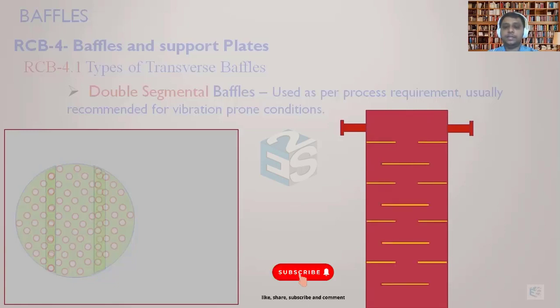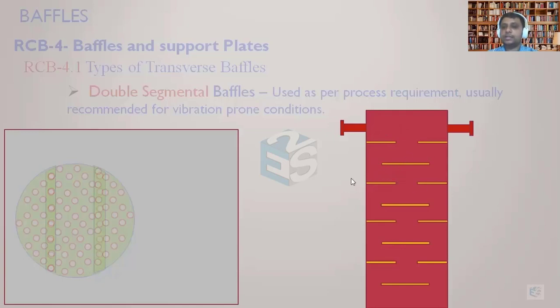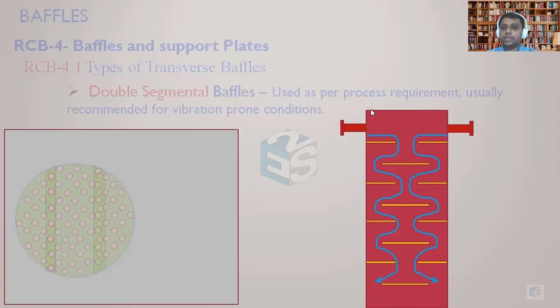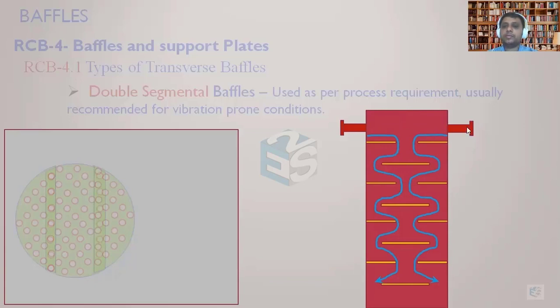Let's understand the flow direction without tubes so we can better understand it. First there are the two side baffles, and then the central one which overlaps — it is not exactly at the center but has some overlap so the fluid falls down and is distributed. The flow from both nozzles follows individual paths. Now imagine the tubes — those very close to the nozzle where there are more chances of flow-induced vibration. These tubes are supported by the initial segments, so their unsupported span is very less. These tubes will be properly protected from vibration.